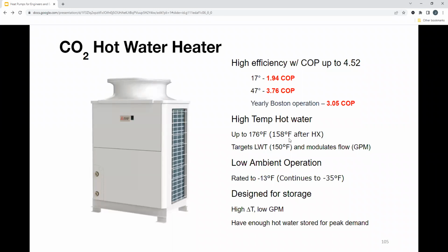So, it targets up to 176. And after that heat exchanger, we're getting about 158. Typically with a storage tank, we're storing water around 140 to 150. And this does have low ambient operation built in, just like our low ambient heat pumps, rated down to -13 degrees. So it can produce hot water at that point, right? And something that's nice is yearly Boston operation is right around 3 COP, which is much more efficient than any kind of electric resistance heater and natural gas being burned.